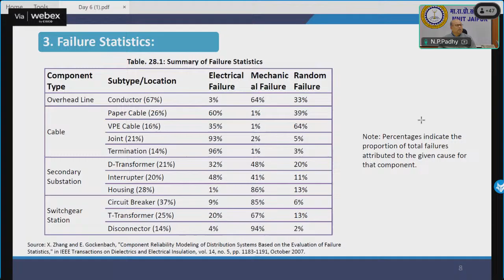So what are the key observations? Overhead conductors: primarily mechanical failures. Cables: failure mostly due to electrical degradation, a very high percentage of electrical failures. Transformers, distribution and transmission transformers: distribution transformers fail due to oil leakage, electrical issues and impulse voltages. Transmission transformers fail mainly due to mechanical stress. Circuit breakers fail due to mechanical causes. Disconnectors fail because of aging and mechanical cycling.